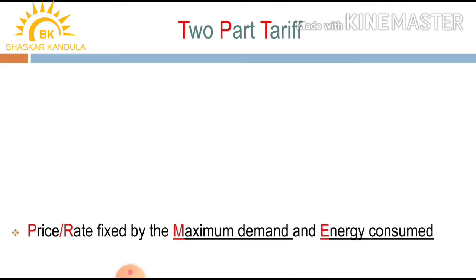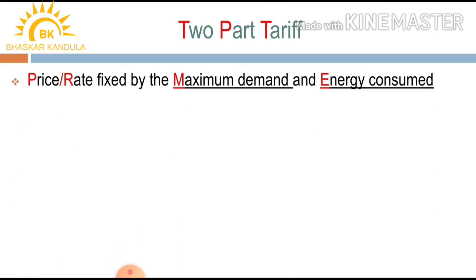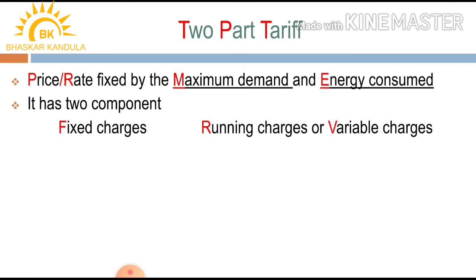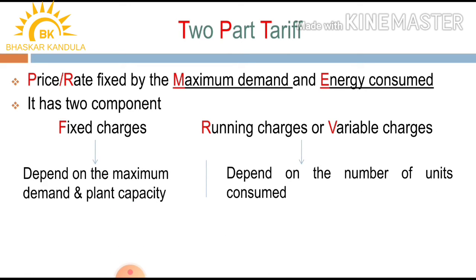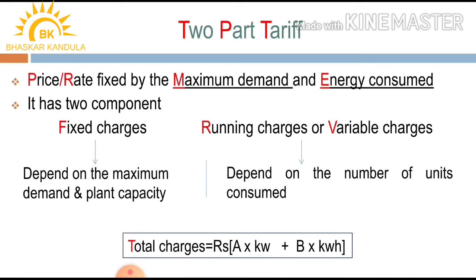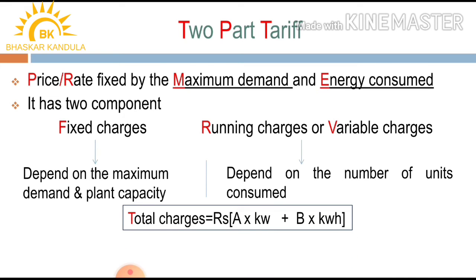In two-part tariff, the price or rate of electrical energy is fixed by the maximum demand and energy consumed. It has two components: fixed charges and running charges or variable charges. The fixed charges depend on the maximum demand and plant capacity, while the running charges depend on the number of units consumed.